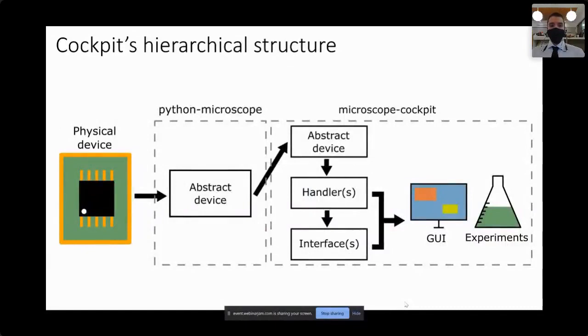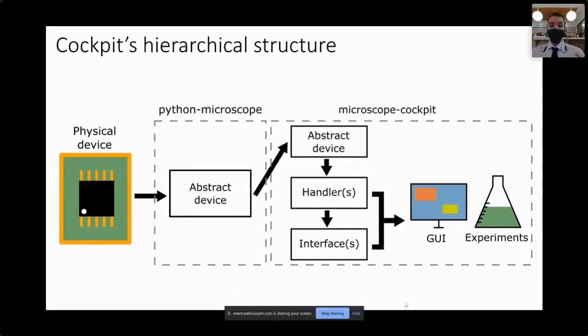The overall structure of the software is such that on one side you have the physical hardware devices, and on the other hand you have the graphical user interface and the ability to perform experiments. The job of Cockpit is to link these two domains together. It starts with Python Microscope, which creates an abstract device representation of the physical device, and then passes that information to Microscope Cockpit, which does further abstraction to use all these components with the user interface and to perform experiments.